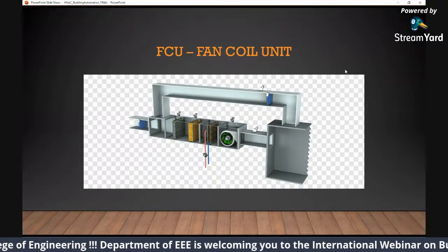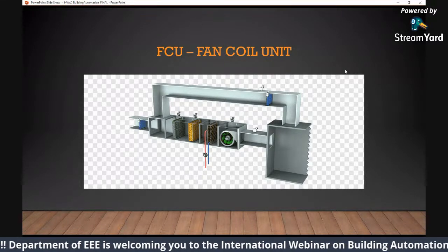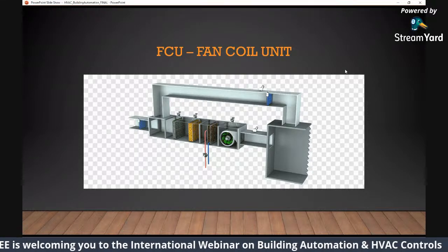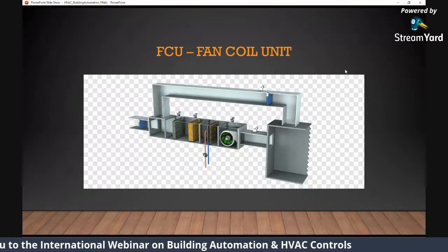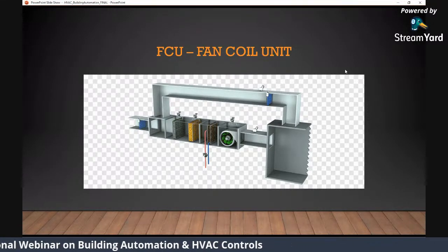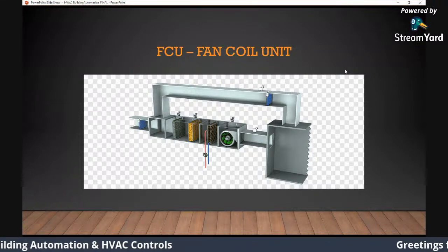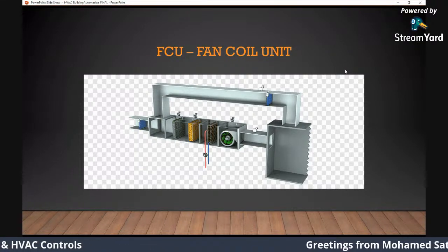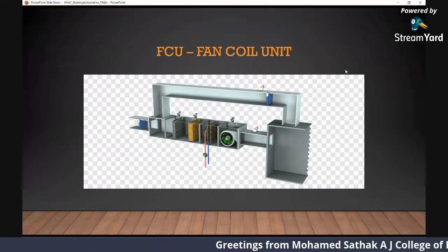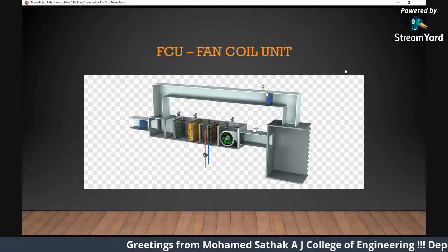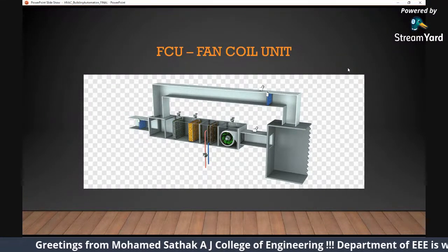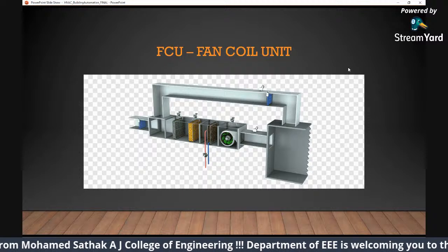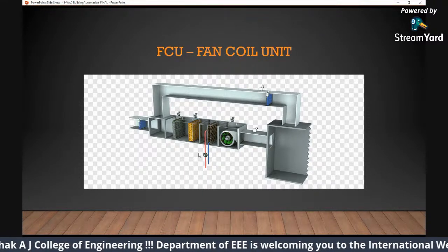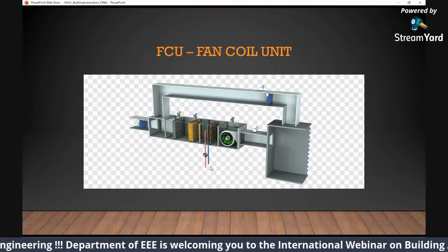Now there are spaces where the AHU cannot supply enough air. So in such units, we mount something called fan coil units. You can call it a table fan, while your AHU is a ceiling fan. Your fan coil unit is a table fan, right? So fan coil units are small, packaged units which supply air to a space where the AHU is not able to reach. It has a fan, it has a filter, it has the same heating and cooling coil.